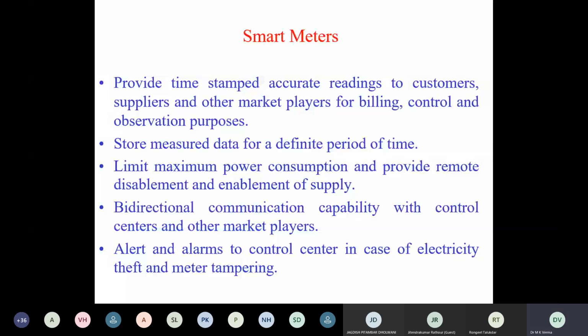Smart meters should be able to limit the maximum power consumption of the consumer and should be able to do remote disablement and enablement. Suppose some consumer is exceeding its power consumption. Suppose some consumer has a 7 kilowatt connection and is drawing 10 kilowatt. Then through smart metering it can be detected, and through remote control the utility should be able to disable its supply. And once it reduces its consumption, it can be enabled. So through smart metering the maximum power consumption of consumers can be limited, and there can be remote disablement and enablement of supply.